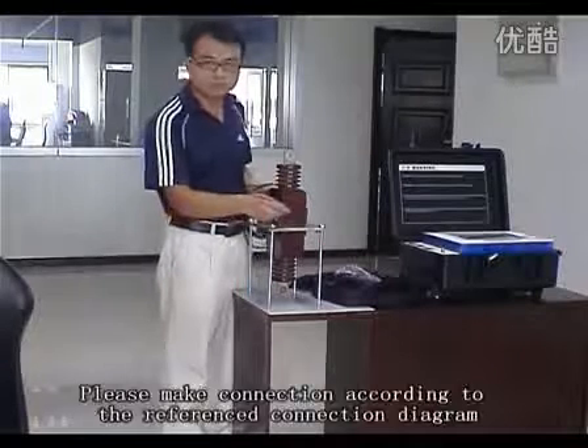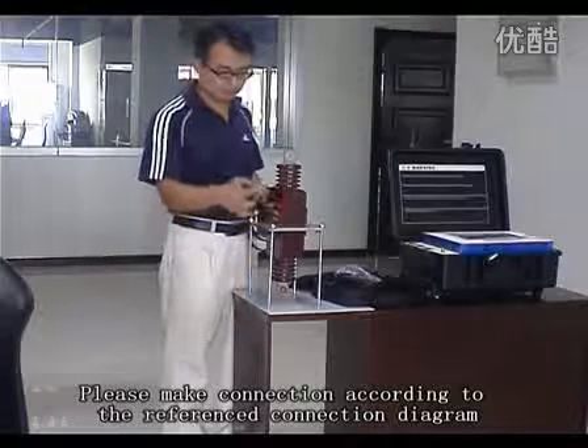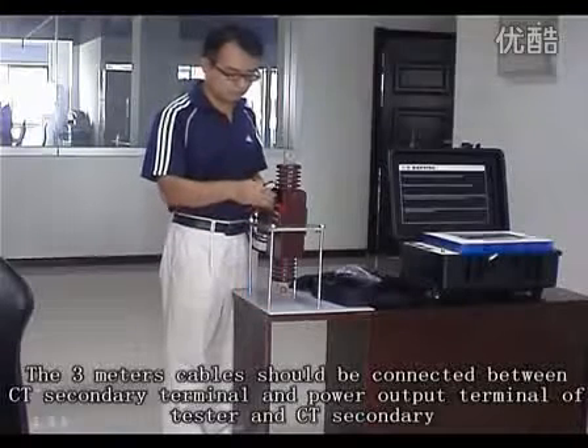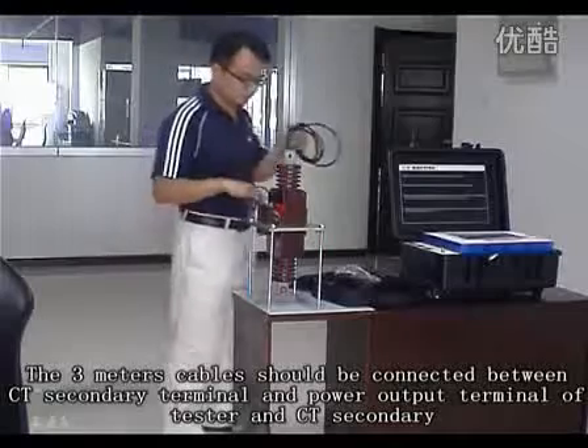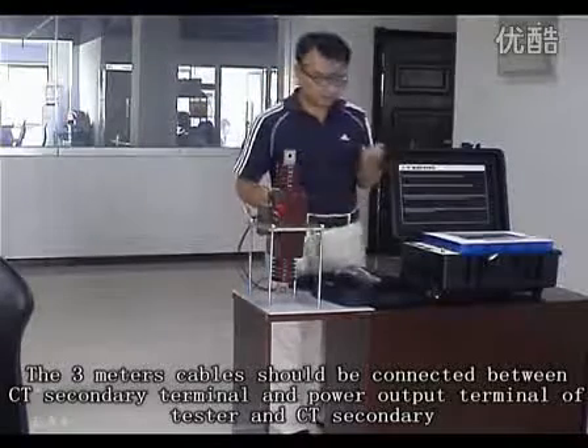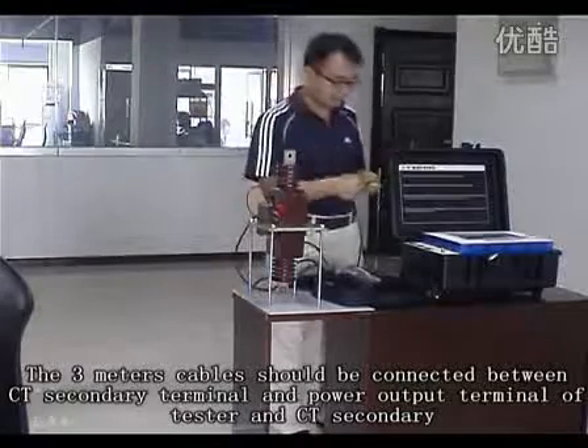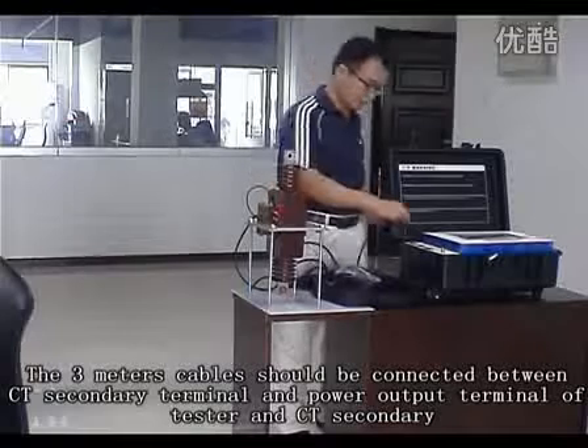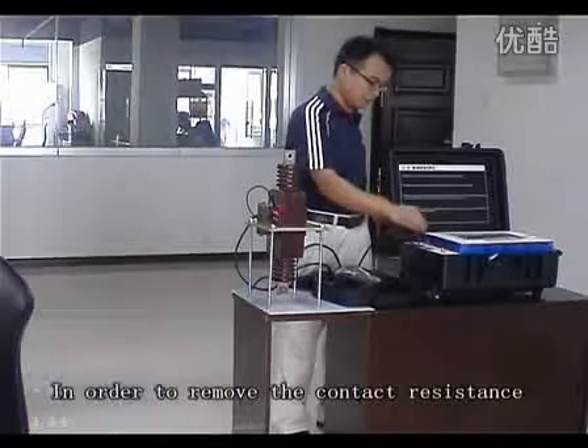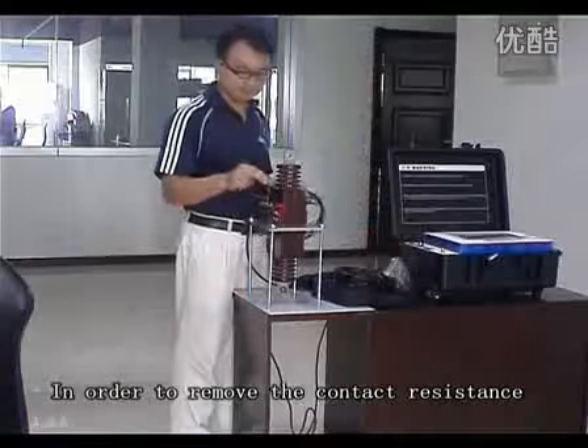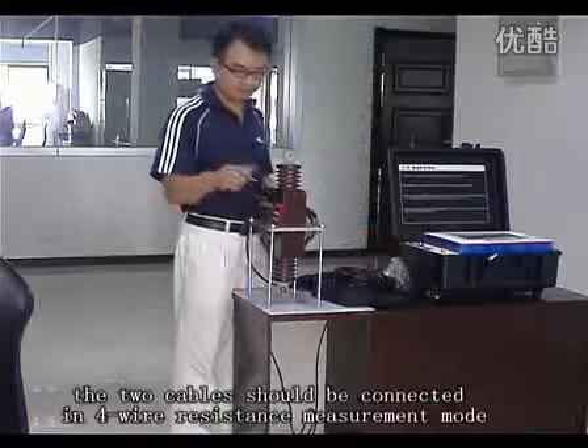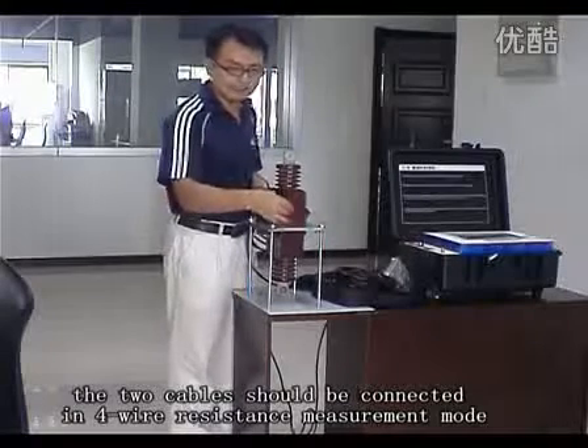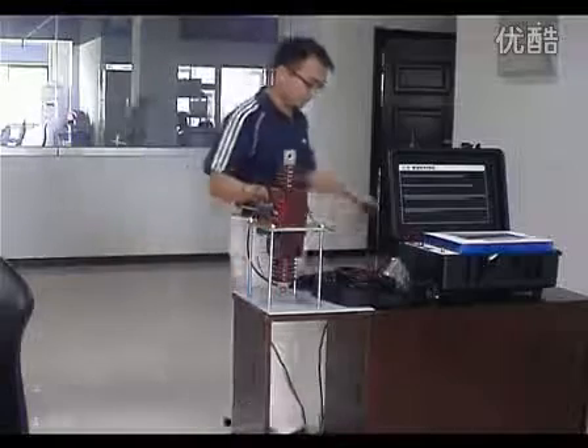Please make connections according to the referenced connection diagram. The 3 meter cables should be connected between the CT secondary terminal and the power output terminal of the tester, and the CT secondary. In order to remove the contact resistance, the two cables should be connected in 4-wire resistance measurement mode.